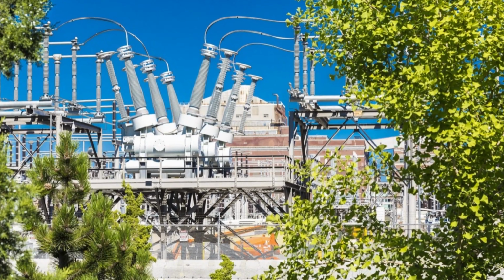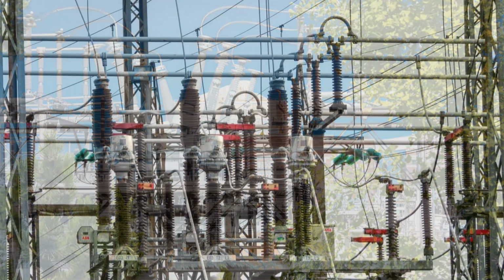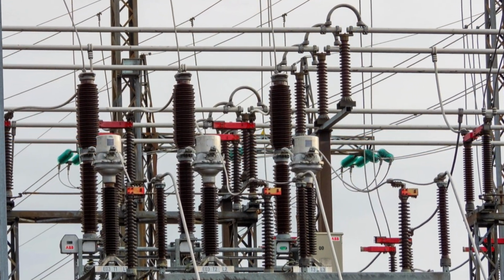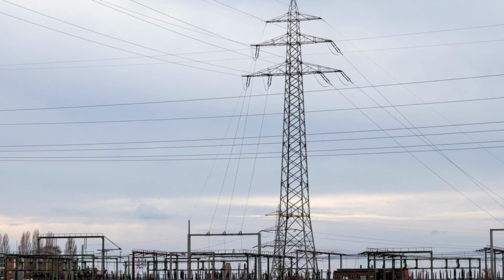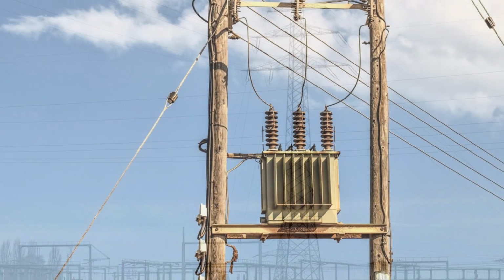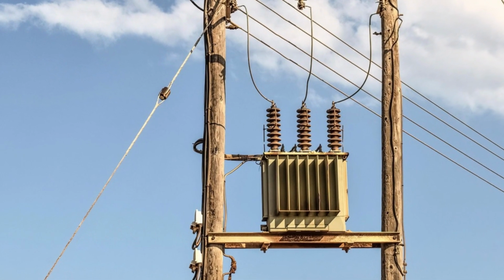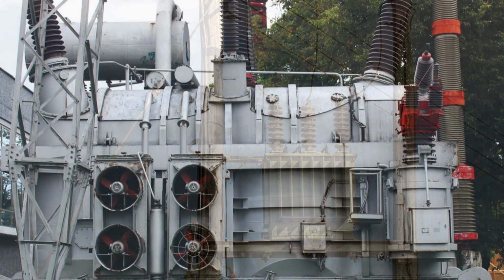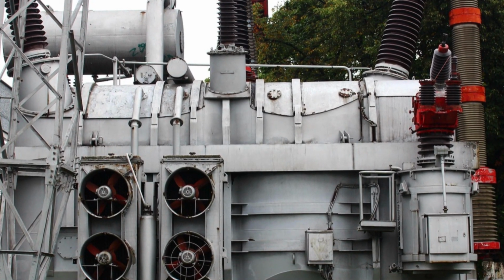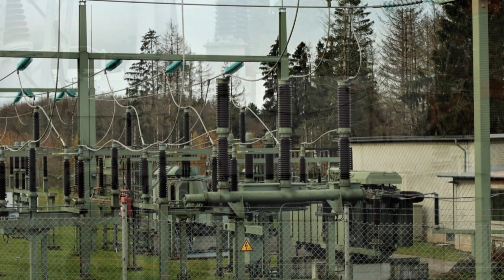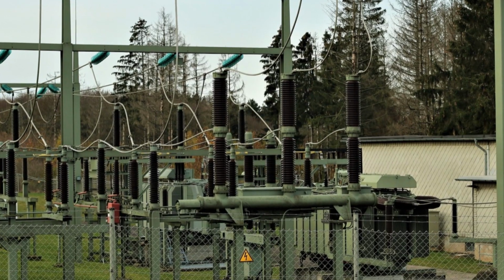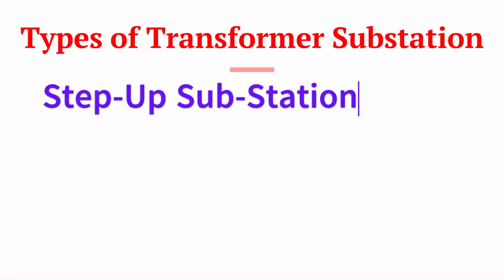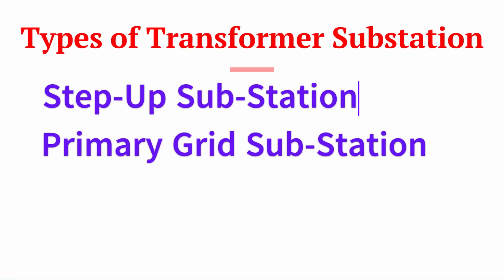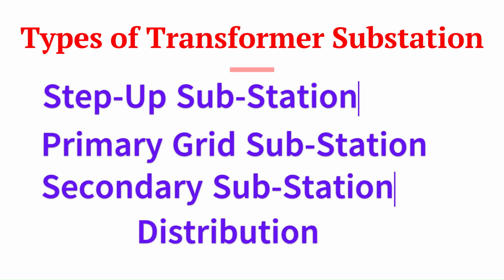Majority of the substations in the power system deal with the changing of voltage level of electric supply. These are known as transformer substations because the transformer is the main component employed to change the voltage level. Now, depending upon the purpose, transformer substations may be classified into step-up substation, primary grid substation, secondary substation, and distribution substation.